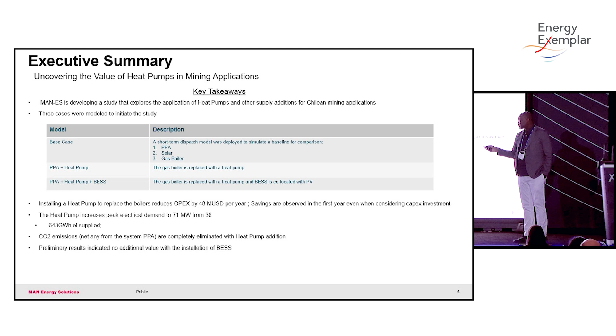The heat pump increased peak demand to 71 megawatts from 38 — we just about doubled the electrical load, but completely eliminated the thermal load. So 643 gigawatt-hours of electricity supplied, but more importantly, all of the CO2 emissions were completely eliminated from the system because we took out the gas boiler and made everything electrical load.